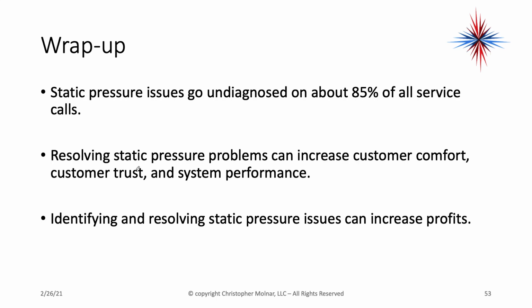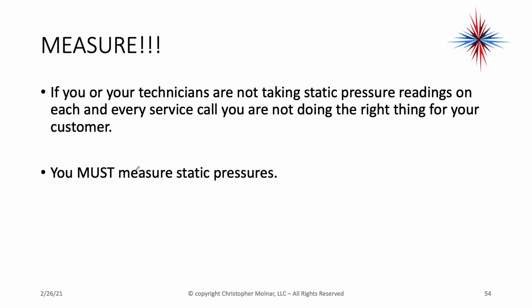Static pressure issues go undiagnosed in about 85% of all service calls. Resolving static pressure problems can increase customer comfort, customer trust, and system performance. Identifying and resolving static pressure issues can increase profits. Measure. If you or your technicians are not taking static pressure readings on each and every service call, you're not doing the right thing for your customer. You must measure static pressures.